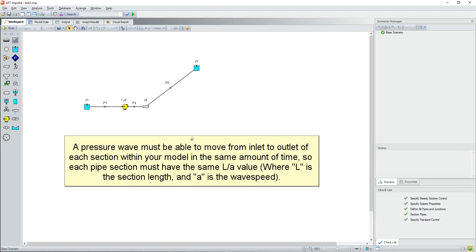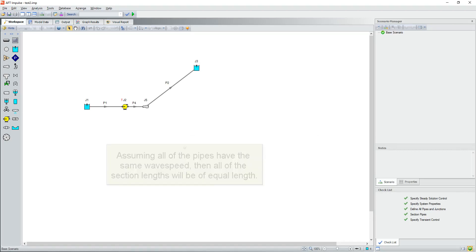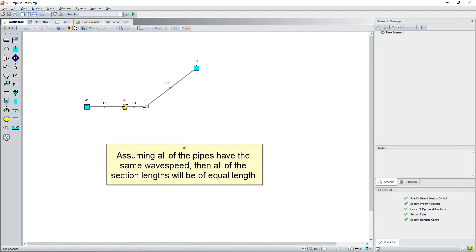A pressure wave must be able to move from inlet to outlet of each section within your model in the same amount of time, so each pipe section must have the same L over A value, where L is the section length and A is the wave speed. Assuming all of the pipes have the same wave speed, then all of the section lengths will be of equal length.